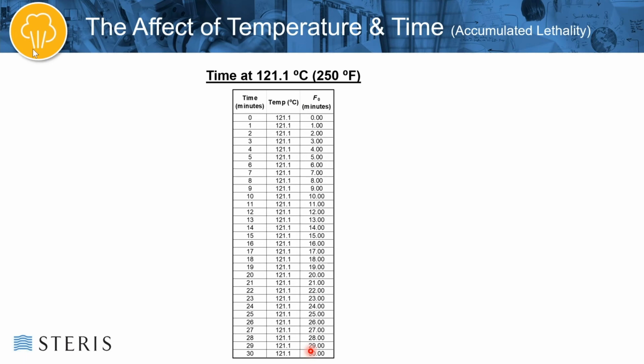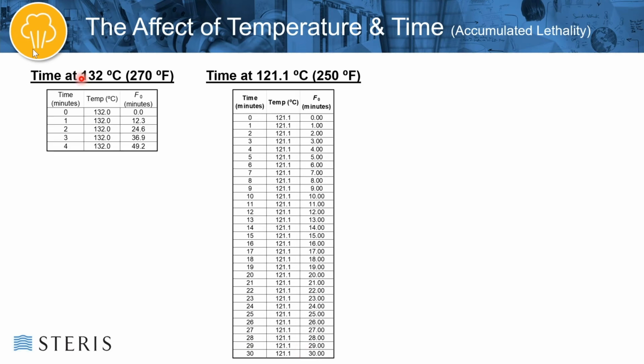So F sub 0 basically means that at 1 minute of 121 degrees Celsius, you will have accumulated 1 minute of accumulated lethality. At 2 minutes, you get 2 minutes, and so on down to 30 minutes. A 30-minute process is a fairly standard cycle at 121 degrees where you've got 30 minutes of accumulated lethality. Now, what happens when we increase the temperature of a sterilization process? At 132 degrees C, we can see that we acquire F sub 0, or accumulated lethality, much faster.